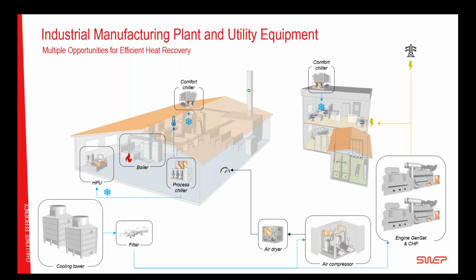In this case, when we start now, we have a cooling tower that is connected to the compressor and the genset to take away the heat, just to, so to say, throw it away, which is a fairly common way. Since they are connected to a brazed plate heat exchanger, we see that they are using a filter to reduce the amount of fouling particles that are around in the system, and we will look into that a little bit later. What are the recommendations for filters when using a brazed plate heat exchanger?